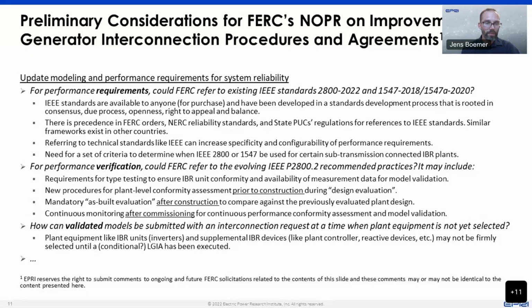With regard to performance verification, that seems to still be one of the bigger gaps in the NOPR. A reference to the evolving 2800.2 could help fill this gap, since there are requirements, or likely to be requirements, for type testing of units, generating measurement data for model validation, new procedures for plant level conformity assessment prior to construction, mandatory as-built evaluation after construction, and continuous monitoring after commissioning.